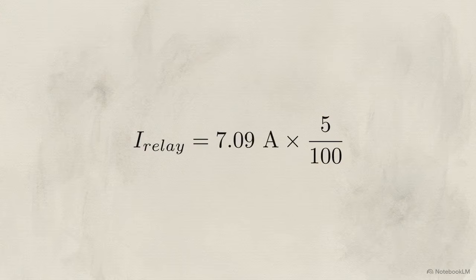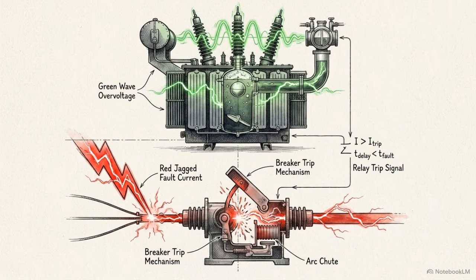We then translate this primary current into a safe secondary current using the physical ratio of the current transformer. Applying a standard 100 to 5 amp ratio yields 0.355 amps, the physical plug setting on the relay. This strict mathematical threshold ensures the transformer ignores temporary, harmless spikes in demand, but acts instantly to isolate the hardware from massive external short circuits.